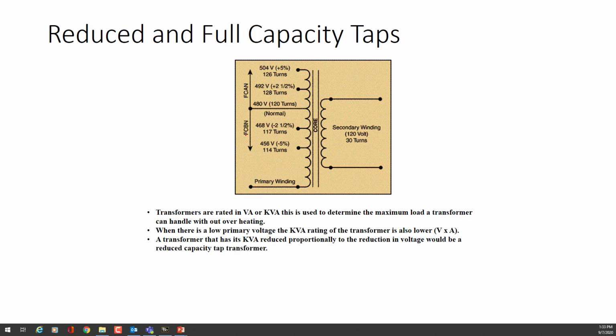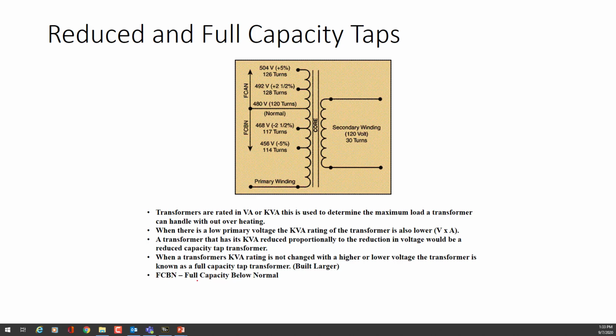So you'll see some acronyms here, like this one says FCBN, and this side says FCAN. So what does that mean? A transformer that has its kVA capacity reduced due to the reduction in voltage would be a reduced capacity tap transformer. When a transformer's kVA rating is not changed with a higher or lower voltage, the transformer is known as a full capacity tap. So it's actually built larger than what's stamped on its nameplate rating in order to take away winding and maintain that same kVA rating. So some of the stuff you'll see is FCBN. What does that stand for? It's a full capacity below normal tap.